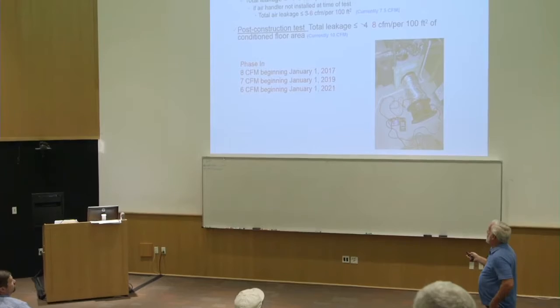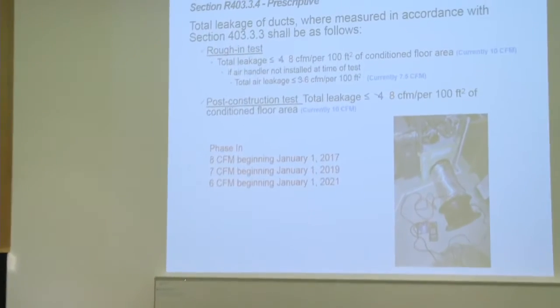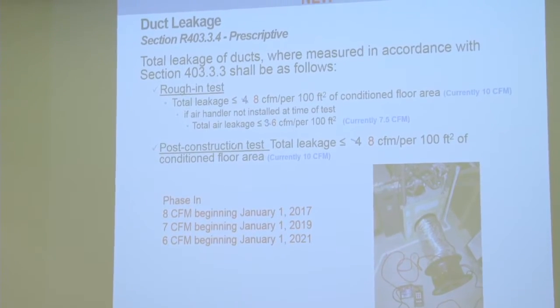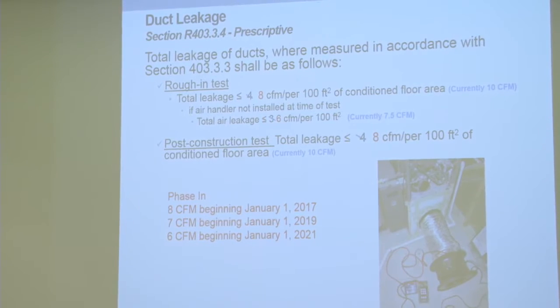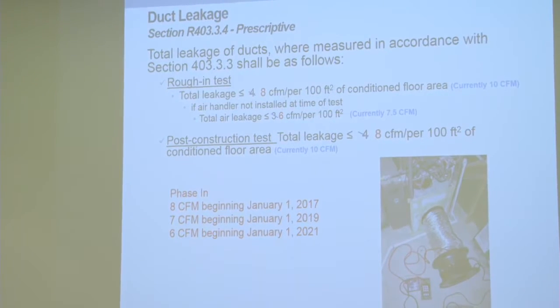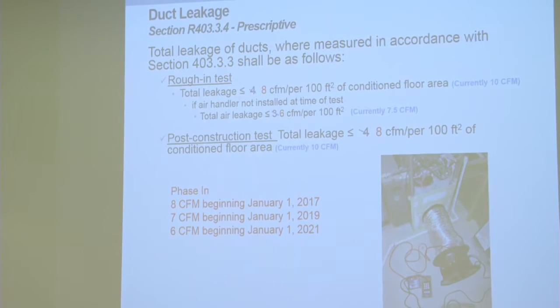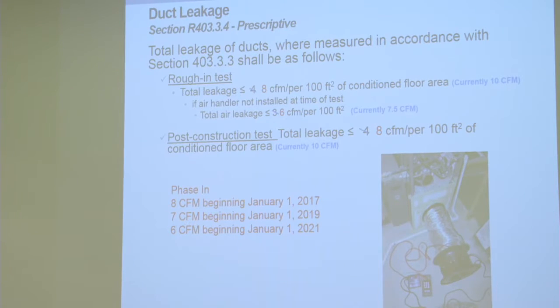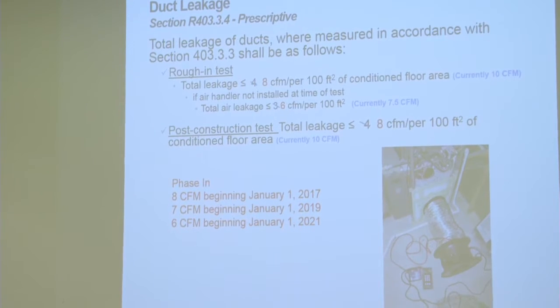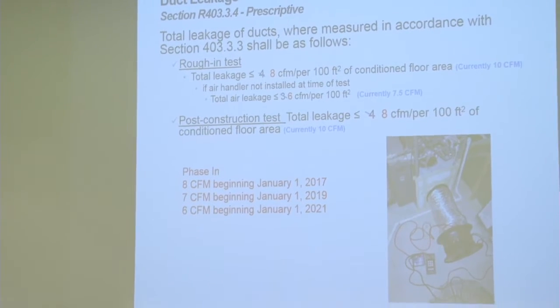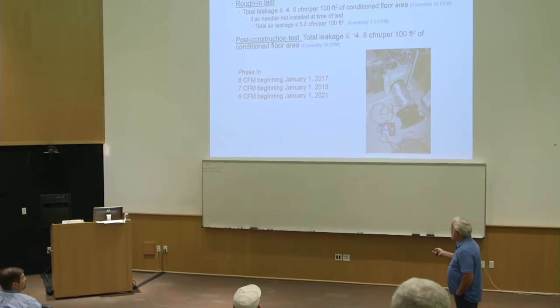And the allowed leakage has been doubled by amendment. So your total leakage just has to be less than or equal to 8 CFM per 100 square feet of conditioned floor area. If you test without the air handler, it's 6. So these were the numbers before the code was adopted, but the 15 code actually says 4 and 3. And these also phase in beginning in January.